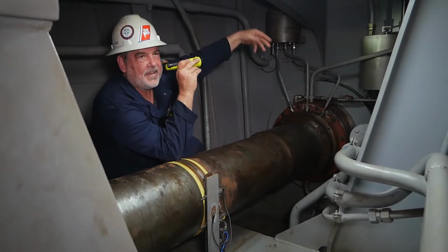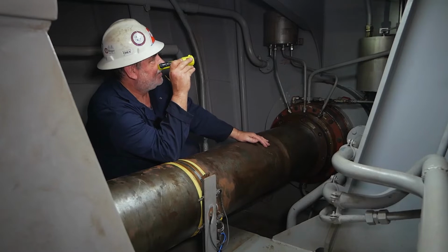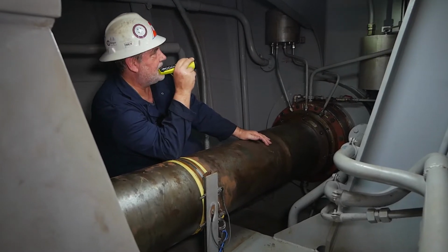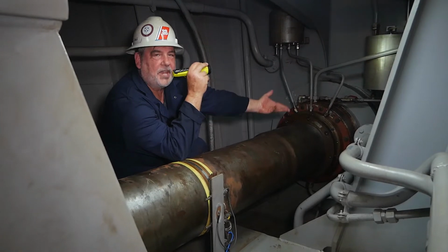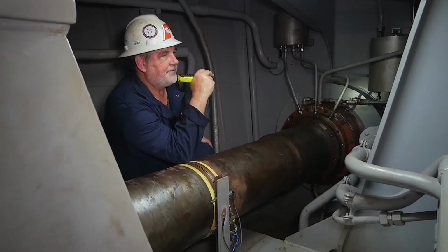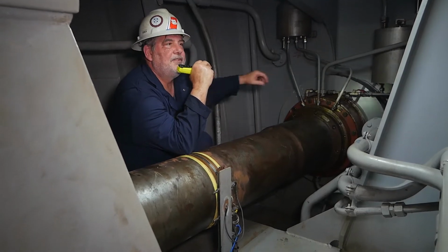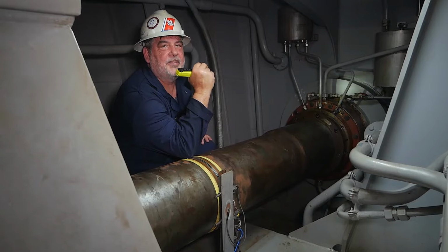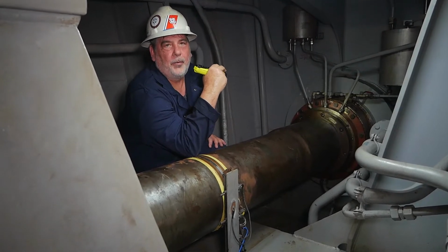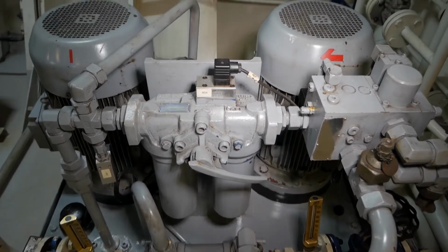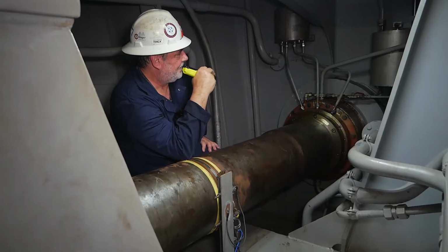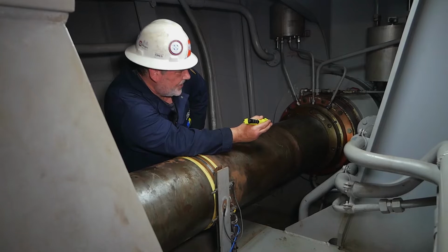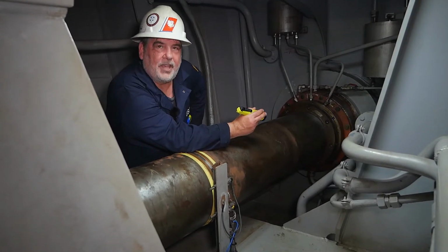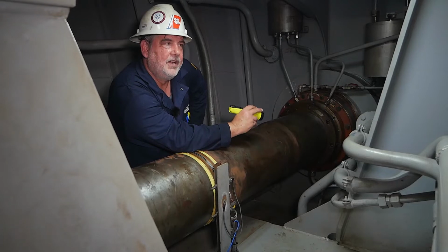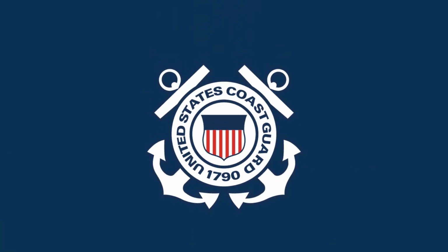On top, you can see that they have high level float switches in them, because you have to ensure they always have oil so that you can keep pressure on the seal. If the seal fails, then you could see oil starting to go out from the shaft seal, and the rainbow in the water would be evidence of a failure. The inability to keep your head tanks full of oil is an indicator that it's leaking. But here's a good shaft seal. Right there you have a thermocouple probe that can also measure the temperature of the shaft seal and be on the lookout for any heat increases.